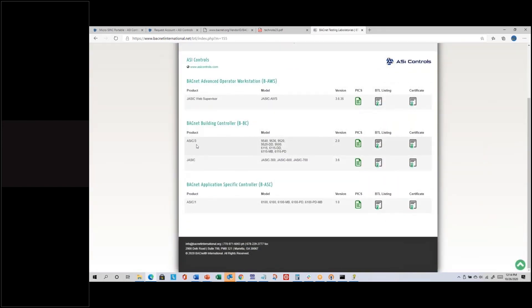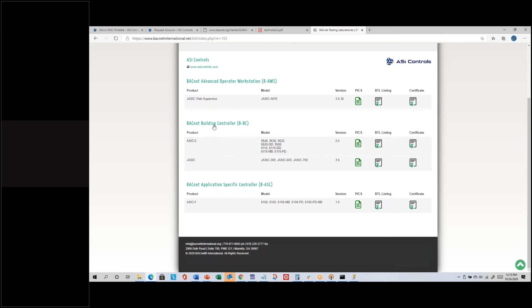Our ASIC/3 controllers are listed as BACnet Building Controllers — BBC is the short name — so all ASIC/3s have the BBC listing. ASIC/1s have the Application Specific Controller listing — BASC. The difference is the types of communication messages each controller type supports. A Building Controller supports more background message types than an Application Specific Controller, and Building Controller is the highest level available for an I/O type controller.